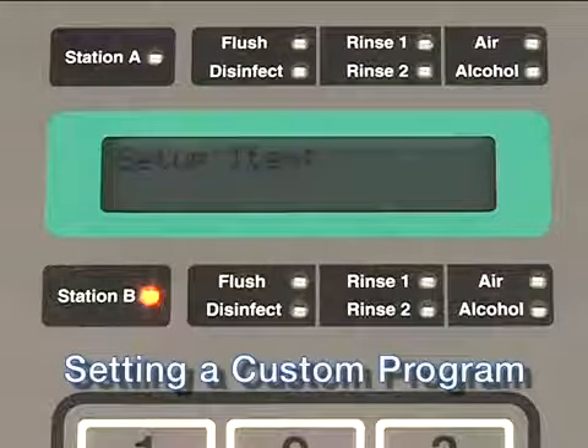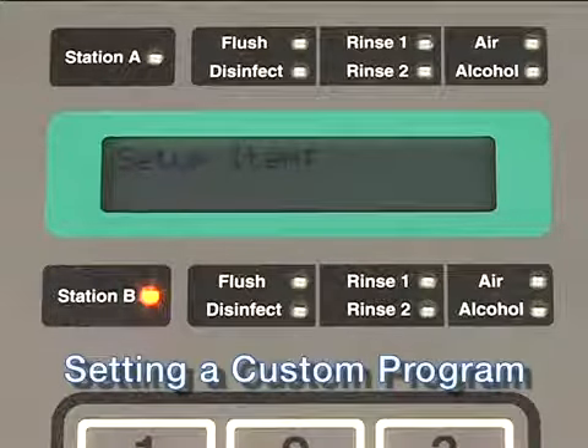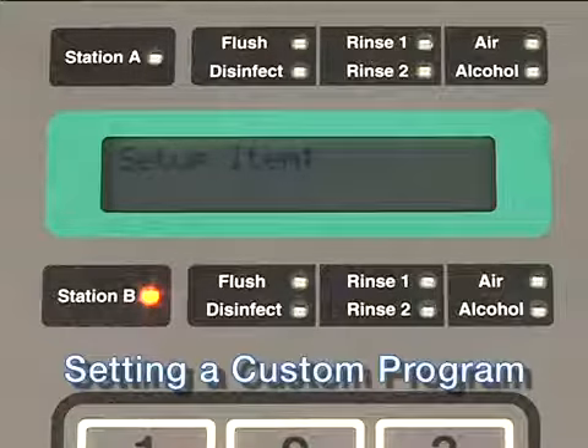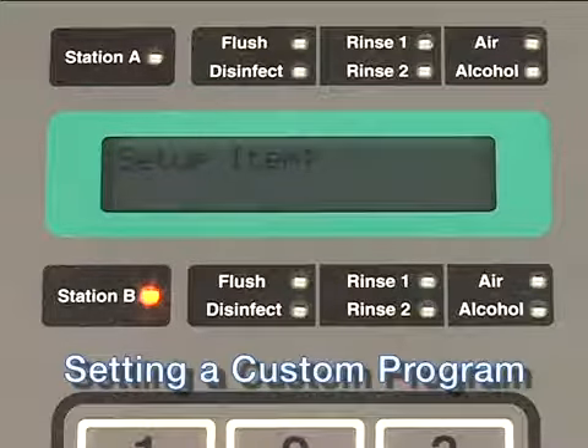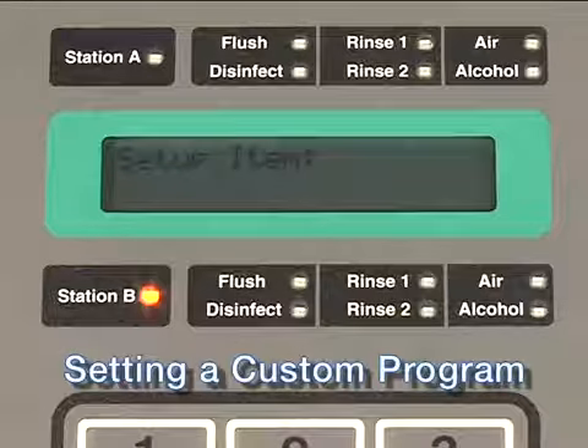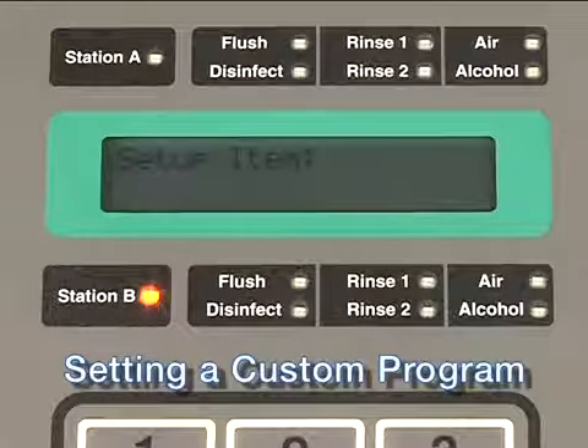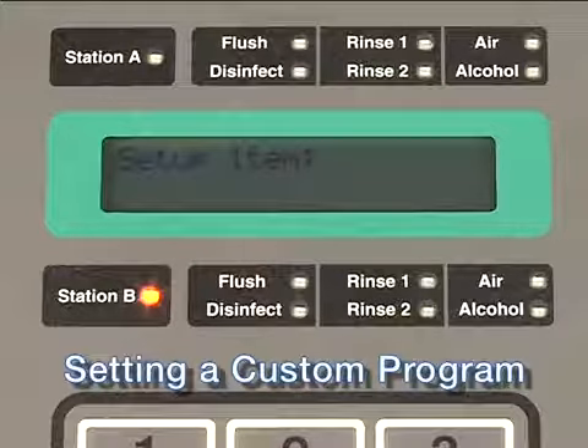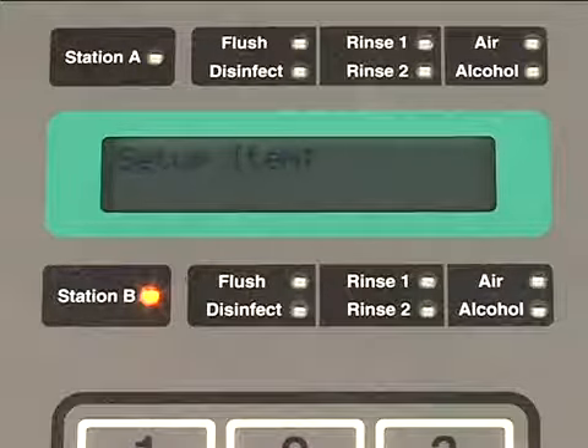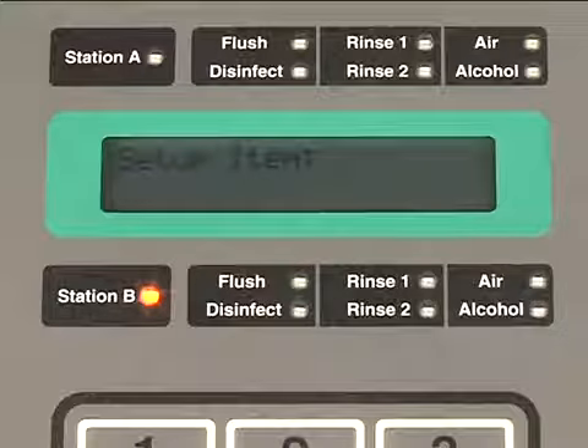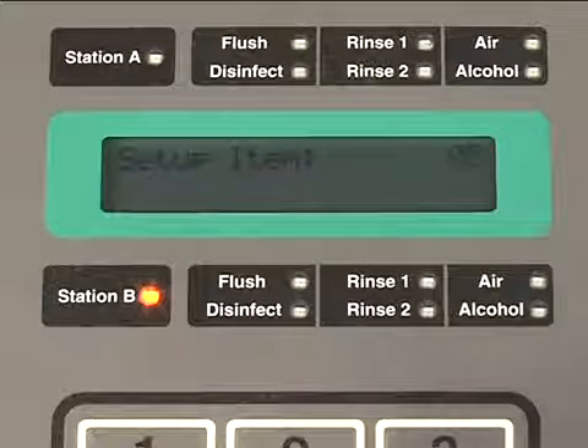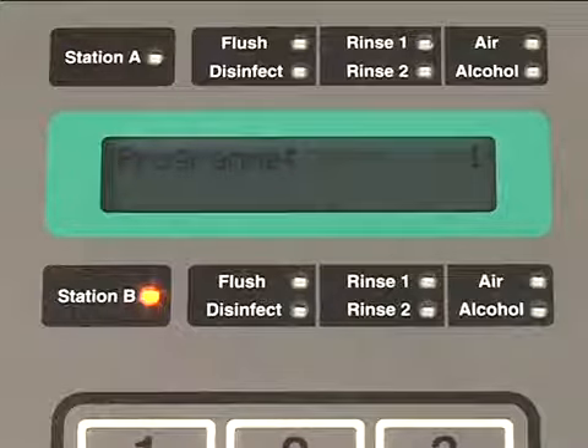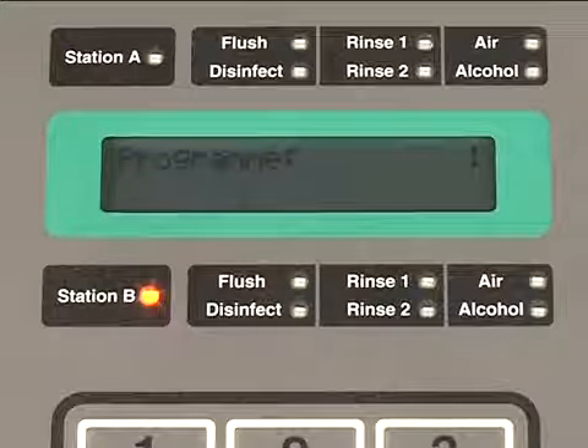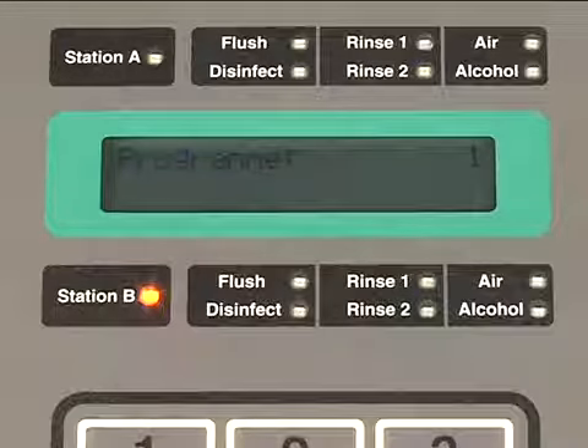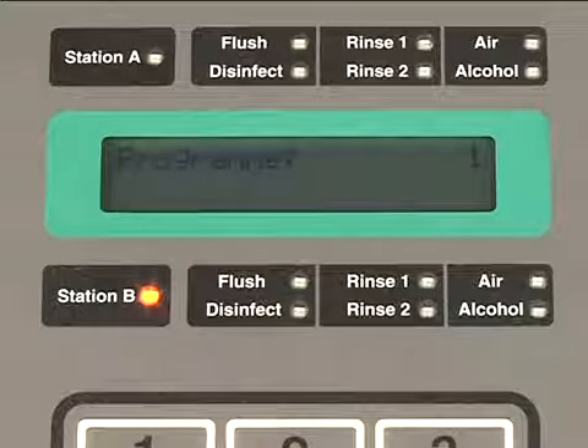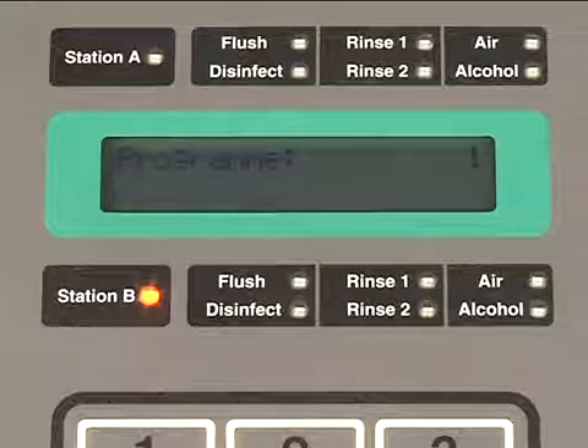Programming your DSD-201. The DSD-201 allows you to set up to 9 custom programs. The settings entered for each program are dependent on the disinfectant that you're using. It's important that you read the label on the disinfectant you're using to ensure the required settings are entered. To access the Custom Program function, press the Setup button. Press 5 on the keypad, then press the Enter button. The first option is to select a number between 1 and 9 to identify the custom program you want to set up. We will set up program number 1.